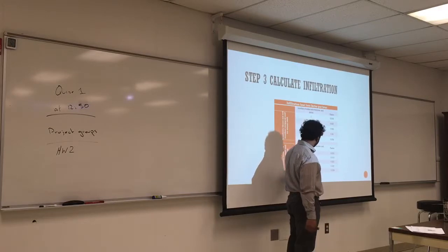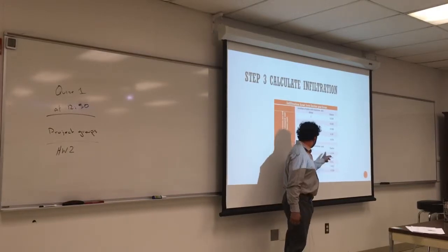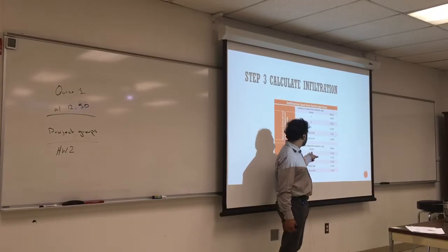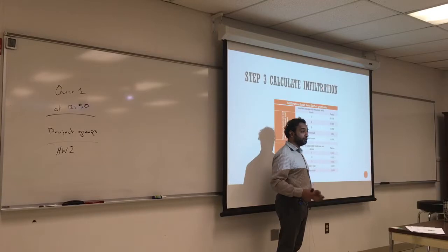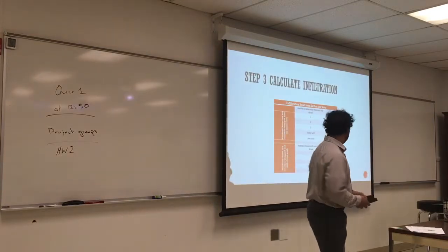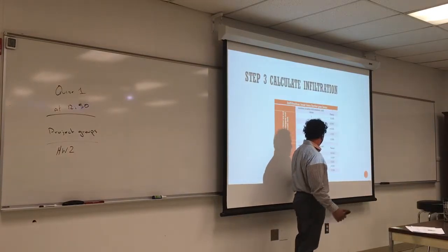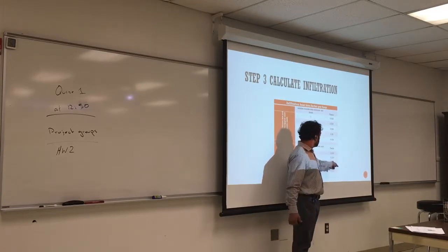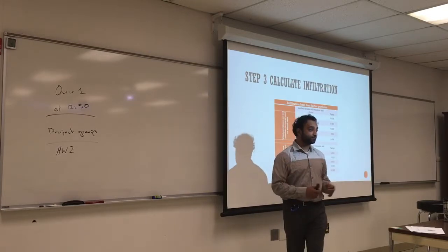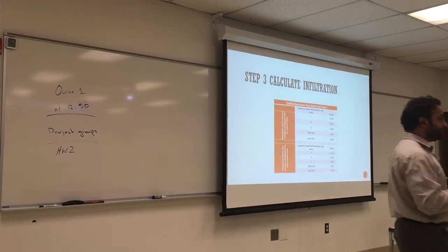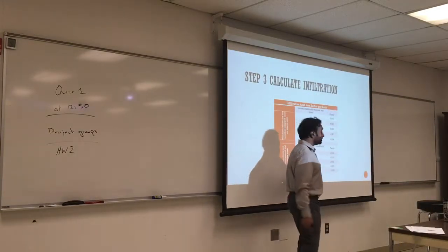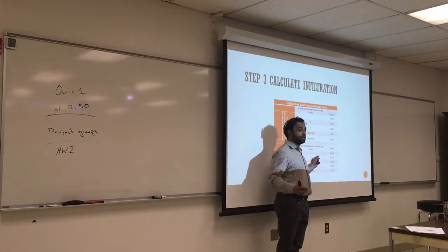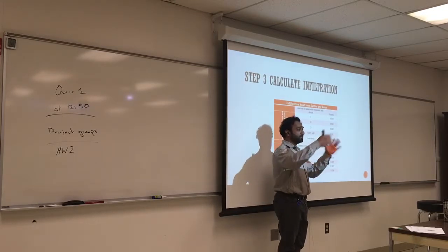And we did that again. That is the factor for the number of sides with windows and doors. So it's not the number of windows, it's the side where the window is. If you have two windows on one side, would that be 0.012 or 0.018? First one. So it's a side, because even if there were two panels, it's about how many sides. You can get one side, two sides, it can be three sides too. Some rooms stick out and they have three sides of windows.